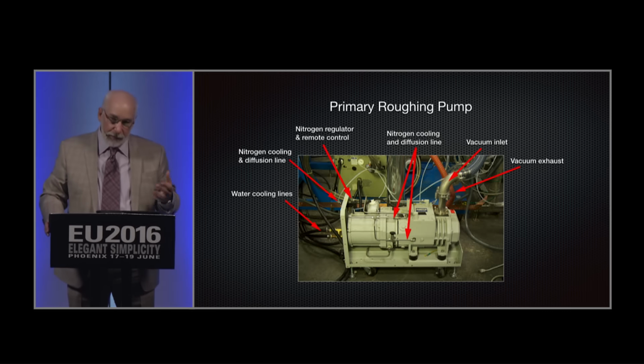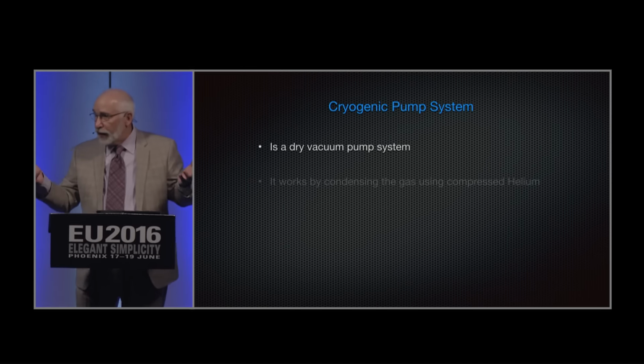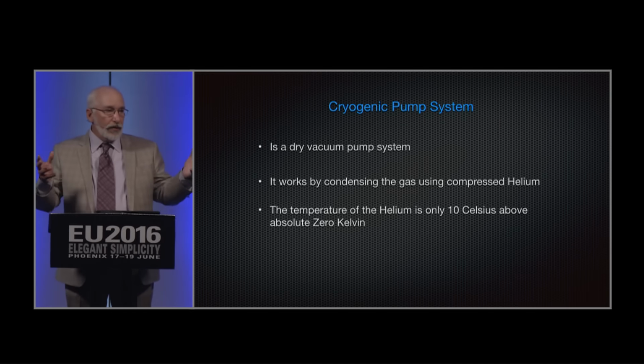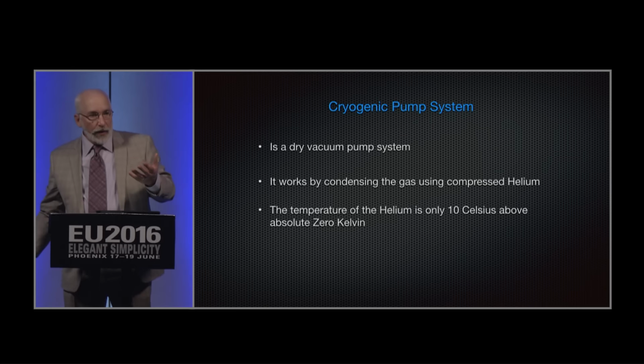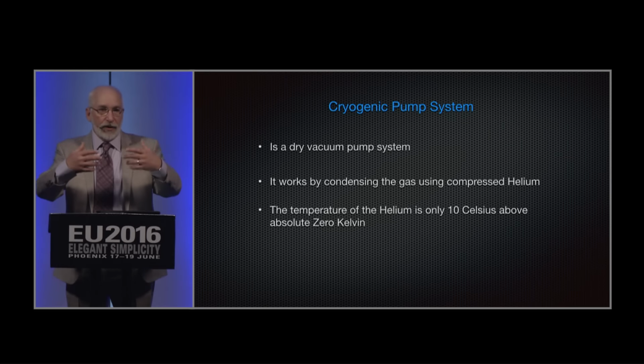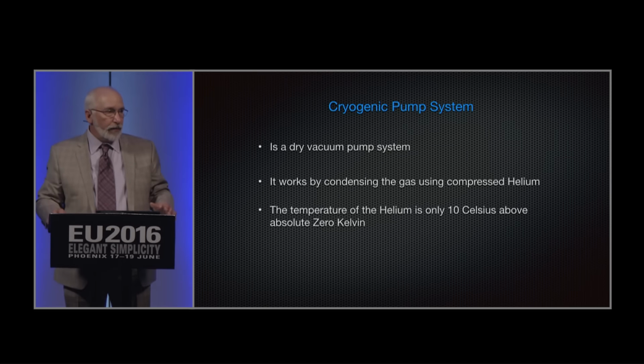Nice pump. Expensive pump. It's a really good pump. It's a dry pump, by the way. Now, that's important because we don't want any hydrocarbons in the chamber other than what we want to put in there. We don't want oil bleeding back through the pump into the chamber, which we think we may have had a problem with in phase one.